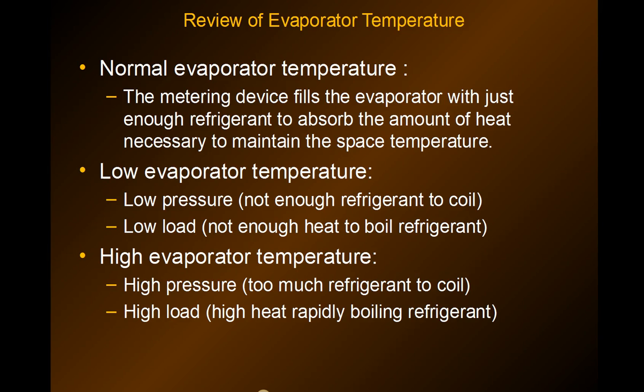A lot of our commercial refrigeration systems are not designed to put 70-degree produce into a prep table to cool it down, and that would be an example of a high load situation.